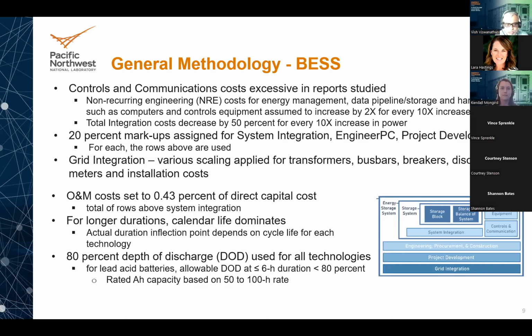Most lead acid batteries have their rated ampere hours based on the 50 to 100 hour rate. At less than or equal to the 6 hour rate, they cannot give you 80% depth of discharge.